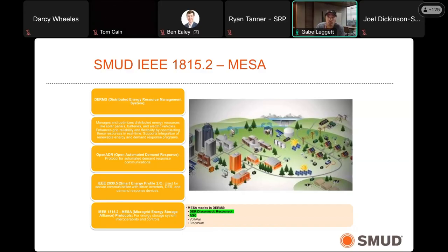What we want to see depends on the agreement with the customer, whether they give us control of the system or it's just monitoring. Either way, even if it's monitoring, we use 1815.2 and those monitoring data points and use cases. We also request the ability to isolate the system in an emergency—DER disconnect and reconnect—and may ask to provide grid stability support, like voltage or frequency support.